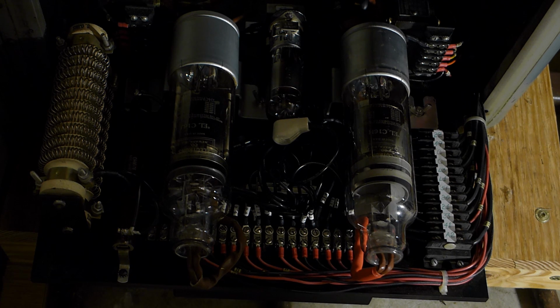Closing the circuit. So now I can control on, which will turn on the center tube, give power to the field. The field has to stay on at all times. If it's ever under power and loses the field, you have a runaway situation with the motor. And so that's one of the safety features. There's also a field loss relay, so if the field ever loses power, it shuts down the machine. So anyway, I'm going to go turn it on real quick.